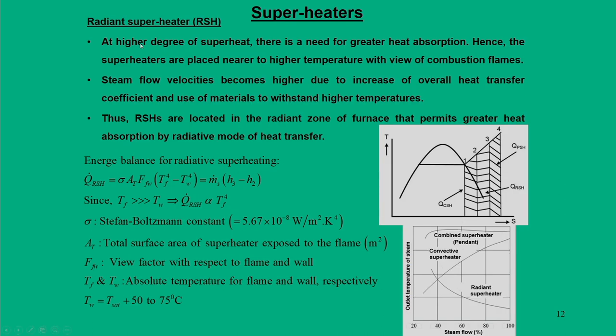The same philosophy can be extended to the radiant superheater, but using the radiation heat transfer equation: Q = σ × A × f × (Tf⁴ − Tw⁴), where σ is the Stefan-Boltzmann constant, f is the view factor, Tf is the flame temperature, and Tw is the wall temperature. In the radiant superheater, steam is exposed to the furnace wall where radiation is predominant, providing greater heat absorption by radiative mode.